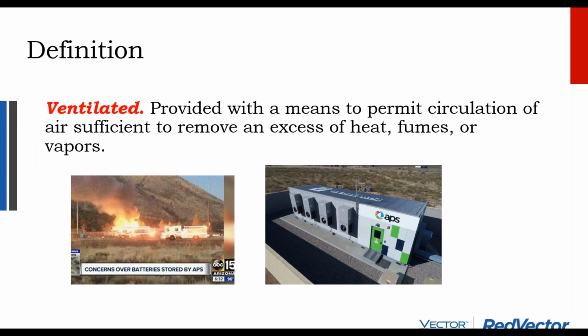Let's talk about ventilation for a minute. Simply put, there are sealed batteries and there are unsealed batteries. Unsealed batteries, like traditional flooded lead acid, produce gas as they're being charged or discharged, and that gas needs to be vented to the outside. Okay, easy enough.